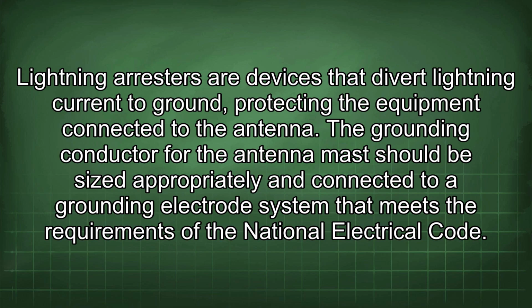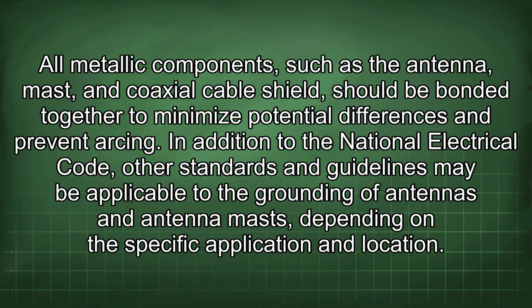The grounding conductor for the antenna mast should be sized appropriately and connected to a grounding electrode system that meets the requirements of the National Electrical Code. All metallic components, such as the antenna, mast, and coaxial cable shield, should be bonded together to minimize potential differences and prevent arcing. In addition to the National Electrical Code, other standards and guidelines may be applicable to the grounding of antennas and antenna masts depending on the specific application and location.